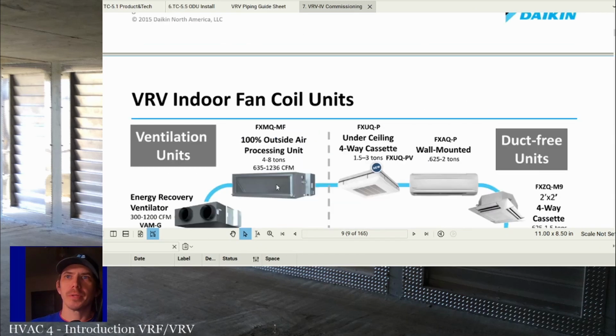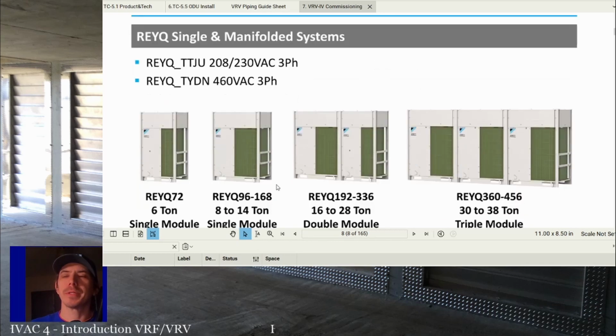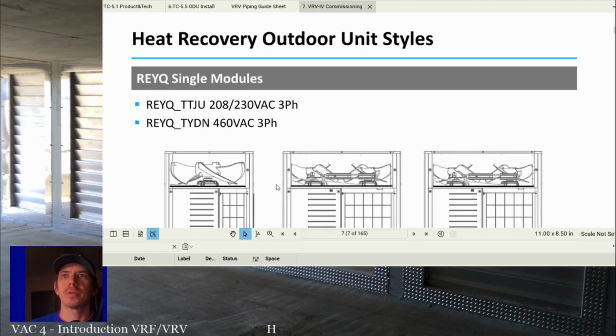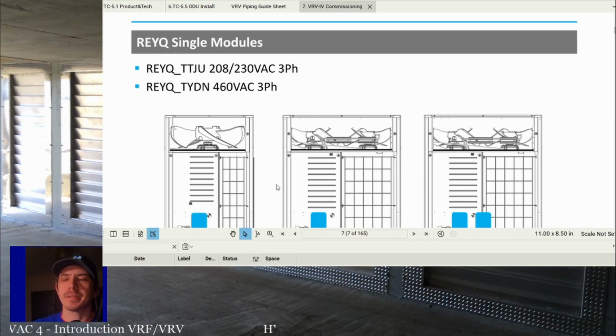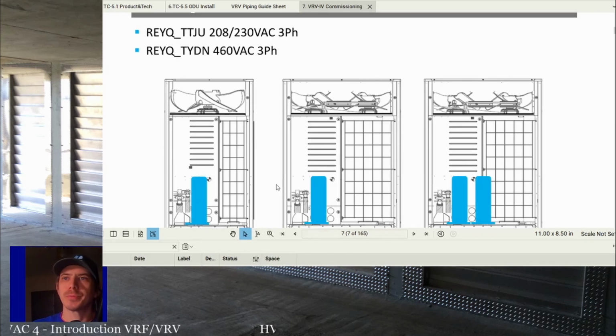When you get to heat recovery, they look the same, right? Heat recovery outdoor units look exactly the same as heat pumps for the most part from the outside. Difference between heat pump and heat recovery. On a heat pump system, you're going to have 2 pipes, and we're going to get into the piping in a bit. But the main thing you've got to remember about heat pump and heat recovery is that on heat pump VRF systems, you have a 2-pipe system. So you're going to have a liquid line and a suction/discharge line, just like any other heat pump, or just like any other mini split style heat pump for the most part.